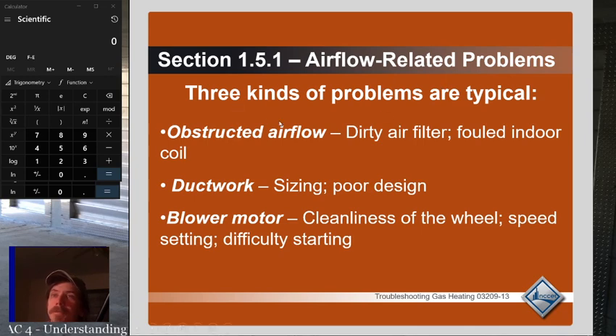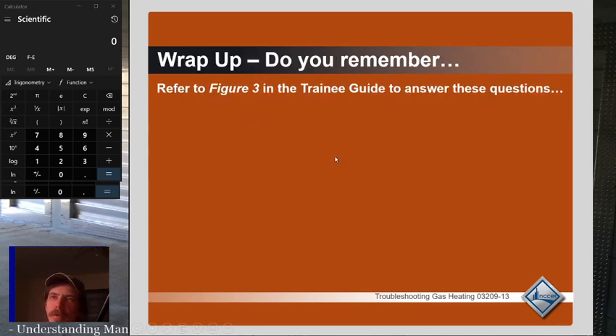Alright, 3 kinds of problems are typical with airflow related problems. Obstructed airflow, which is dirty air filter or fouled indoor coil. Ductwork, sizing, or poor design. Undersized ductwork is extremely common. Blower motor, cleanliness of the wheel, speed setting, or difficulty starting. Those are the typical things that you're going to find affect airflow.